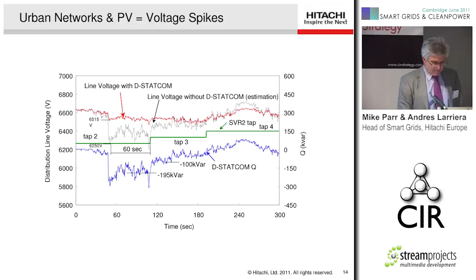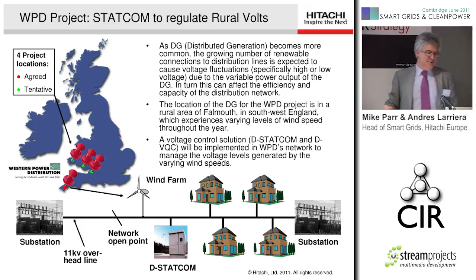Andreas mentioned the project we've got with Western Power. The bottom part shows two substations, one at each end, both primary subs. There's a network open point, because in rural networks you normally have an open point - well, in urban networks too, unless you run a mesh network. You've got a wind farm not far from the network open point, and the first part of our project is to install a D-STATCOM reasonably close to the wind farm.